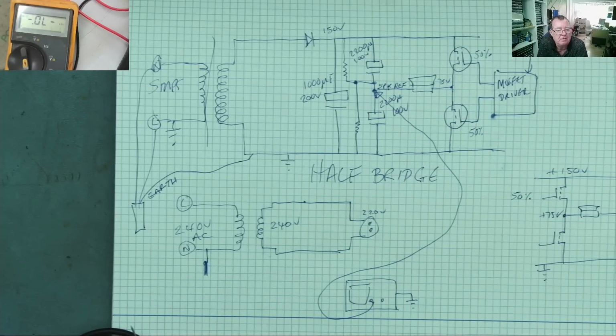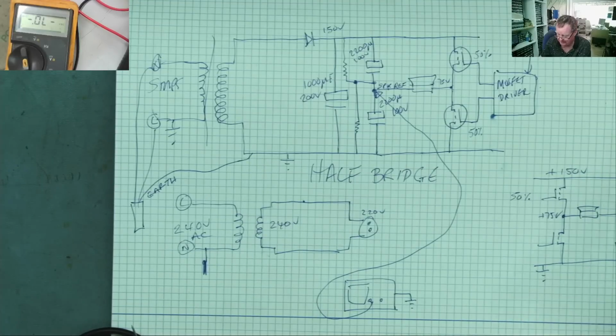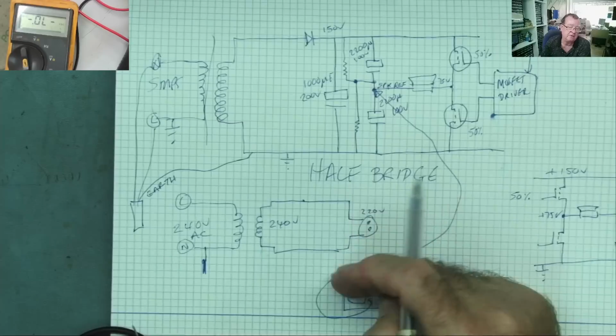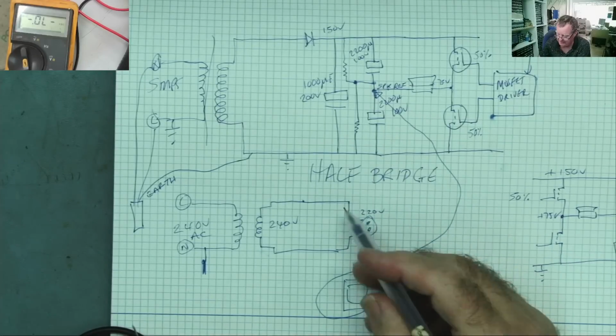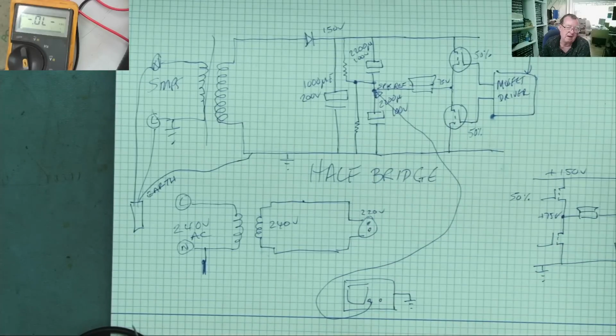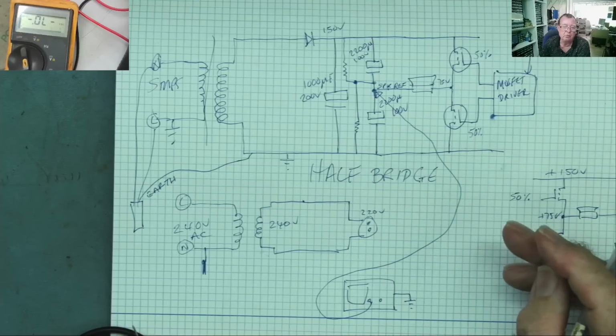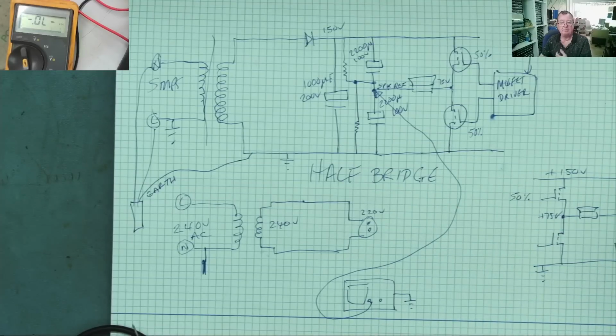This is a very good reason why you should always have an isolation transformer. The other reason is that I can touch the live or neutral here and not get a shock, because neither of the wires I'm touching is grounded. Whichever one I touch automatically just becomes ground through me, but no current is flowing.